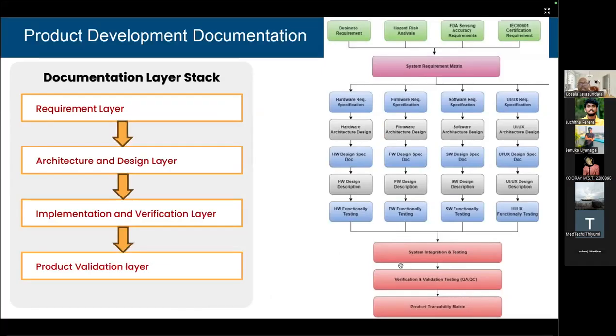And then we have verification and validation testing, which should be done by a separate dedicated QA department, which cannot be altered. Verification and validation cannot be done by the same engineers who are developing the software or UI UX. That should be a separate team.